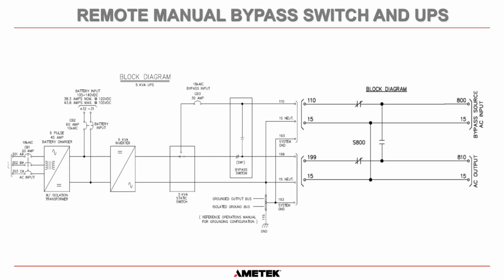Okay, we've got a few more questions coming in. How can we emergency shut down a UPS? Is it removing the optical fiber cable from the static switch when our display board is not working and the system to transfer to the alternate line?